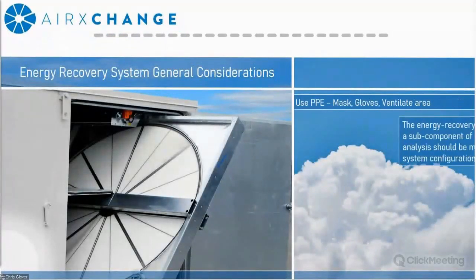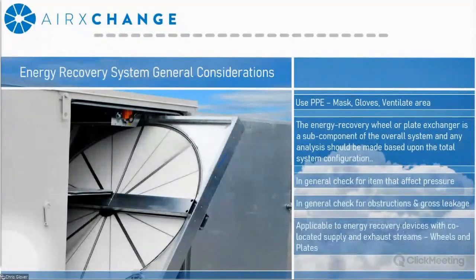So the guidance that I'm going to share here, I mentioned before, is based on the TC 5.5 practical guidance operation of energy recovery devices. That document is available on the ASHRAE website, and it's really intended for building operators. First things first, safety. Always make sure that you're using the proper personal protective equipment and that you're adequately ventilating the area and the unit that you're going to be viewing. It's important to keep in mind that the energy recovery component is also a subcomponent of a much larger system, and other components within that system have an effect on the energy recovery's operation, and you're going to need to take that into consideration during the inspection.